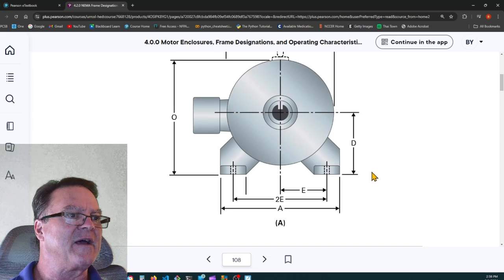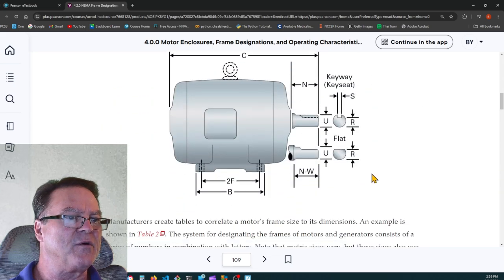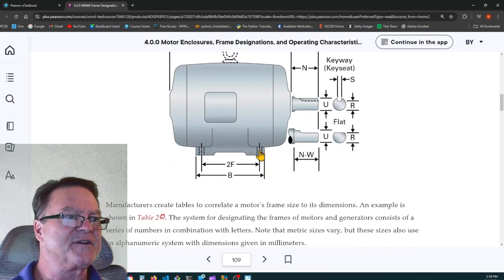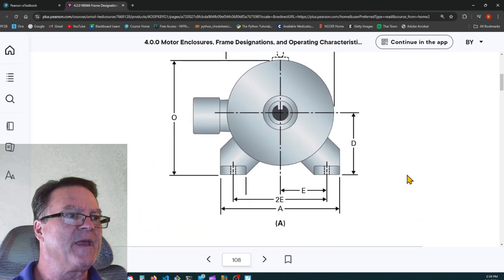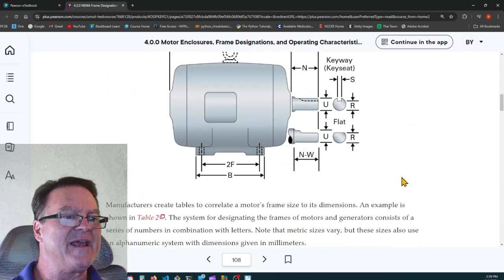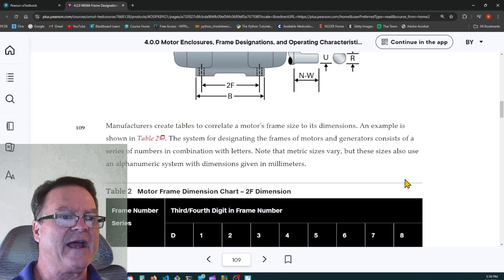Well, we can't see that when it's sideways. Here you go. Looking at it sideways. From center to center of the anchoring bolts is the 2F dimension. All of these dimensions are given, and it's in the name of the actual motor. It's in the number. Manufacturers create tables to correlate a motor's frame size to its dimensions. An example is shown in Table 2.